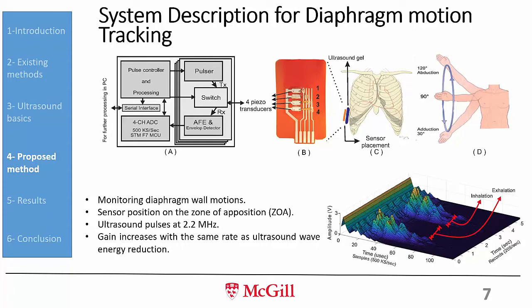So what we decided to use is an array of 4 piezo transducers. So even during body movement, if one of the transducers gets displaced from the gap between the ribs, at least there will be one transducer that can see the diaphragm through the gaps between the two ribs. That's why we had an array of 4 transducers.